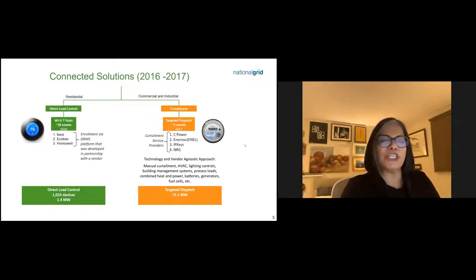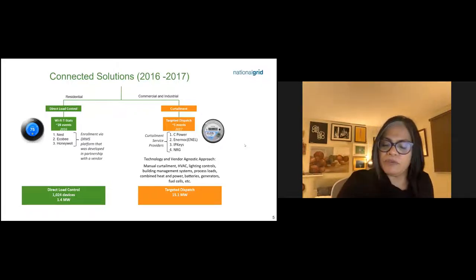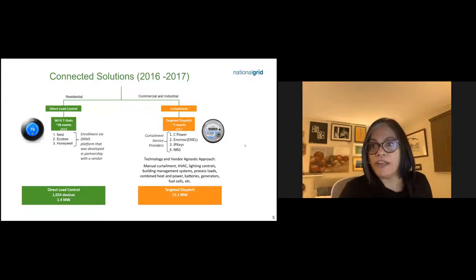And then on the commercial and industrial side, the way the program runs is we have curtailment service providers who actually reach out to customers for load reduction. And we look at calling events and you can see the reduction in load. Typically with the targeted dispatch commercial program, you have about five events in a year. So it is a pretty small window of events, while on the residential side, you're looking at a lot more events. In the 2016-17 timeframe, we had about 1,000 devices enrolled in the program with a reduction of about 1.4 megawatts. With the targeted dispatch program, we saw about a 15.1 megawatt reduction.